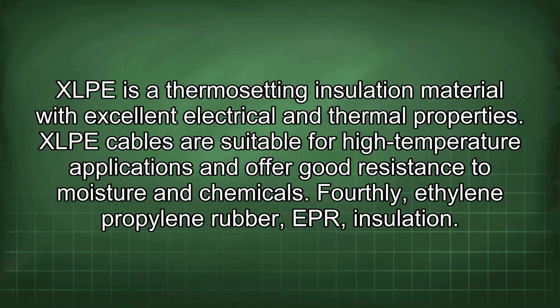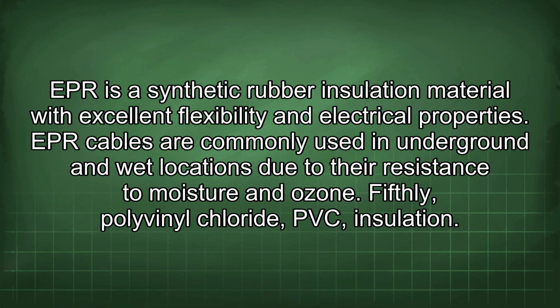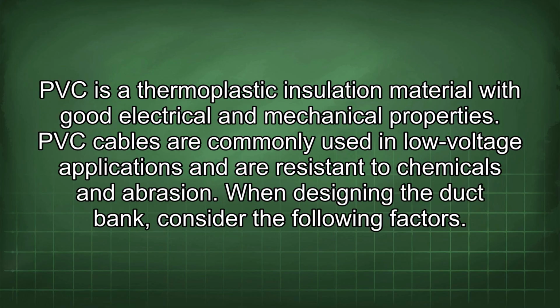Fourthly, ethylene propylene rubber (EPR) insulation. EPR is a synthetic rubber insulation material with excellent flexibility and electrical properties. EPR cables are commonly used in underground and wet locations due to their resistance to moisture and ozone. Fifthly, polyvinyl chloride (PVC) insulation. PVC is a thermoplastic insulation material with good electrical and mechanical properties. PVC cables are commonly used in low-voltage applications and are resistant to chemicals and abrasion. When designing the duct bank, consider the following factors.